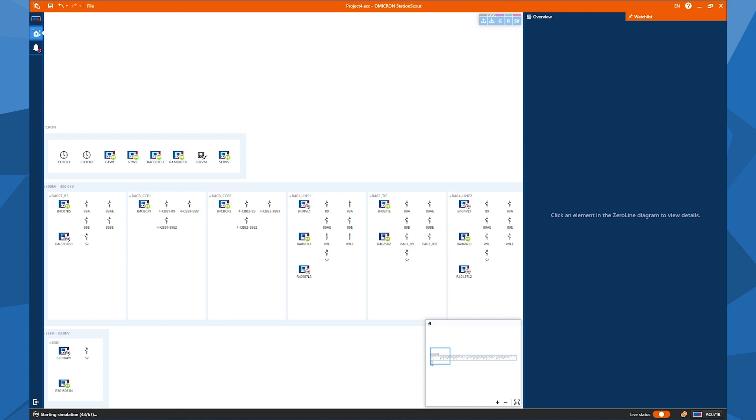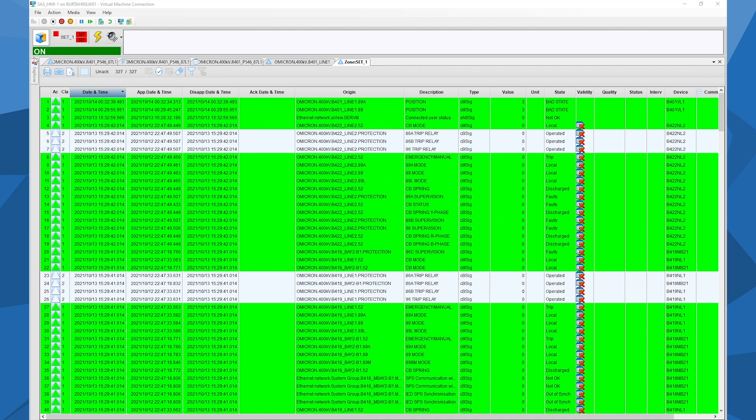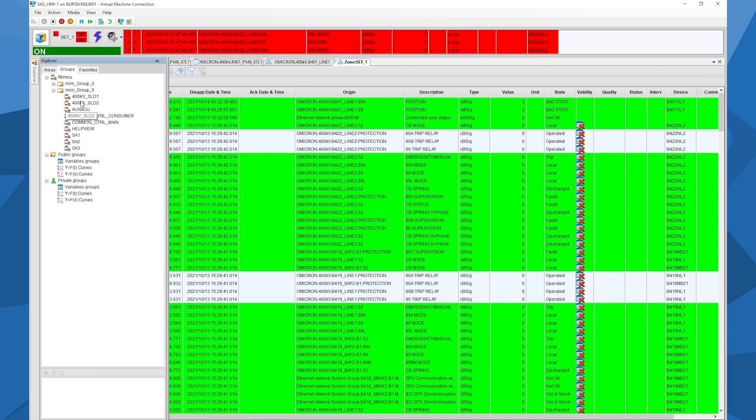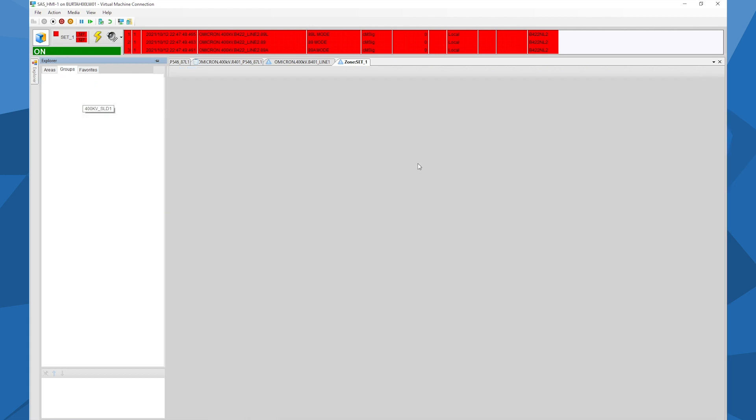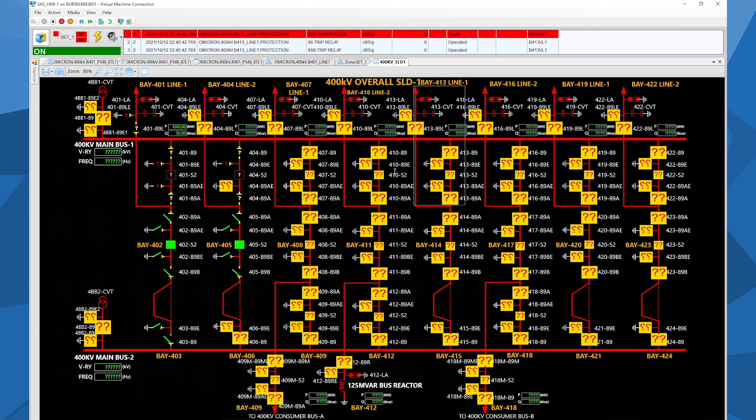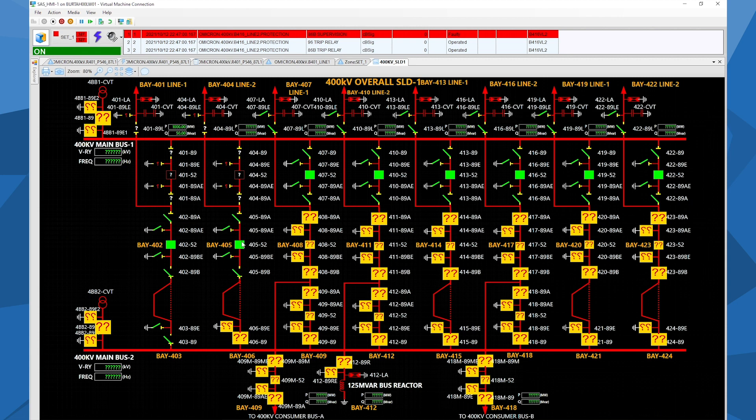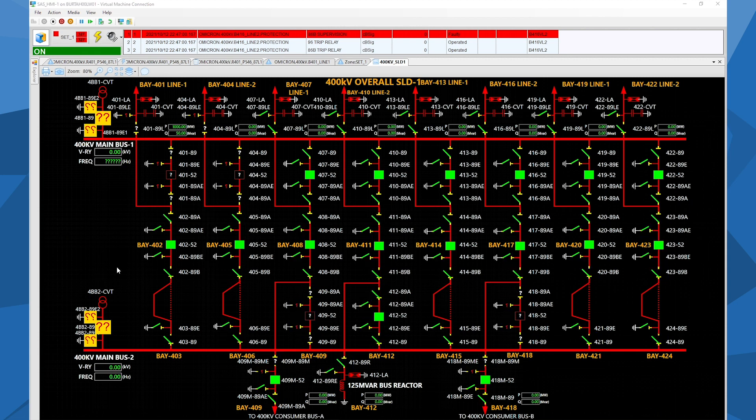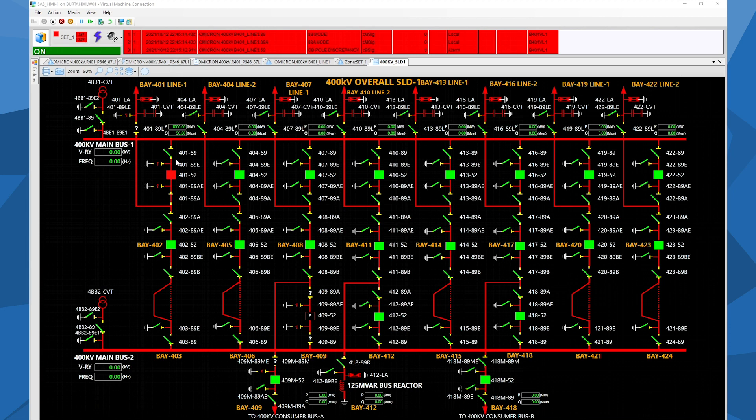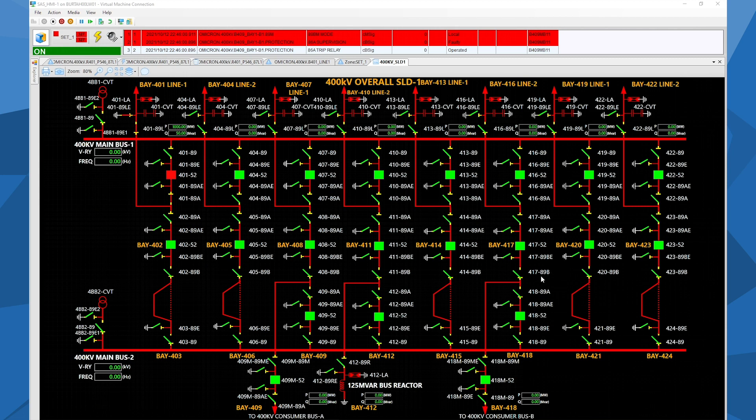Okay, so this shows us a hint that which IEDs we expect to see the positions and all the other signals which are communicating out to the SCADA. And when the HMI systems comes online, we can switch to the single line diagram, which is the general overview of the HMI that shows us all the bays and all the positions within the bays. So now you see that some of the bays have the valid positions taken from the Station Scout online, and some of the bays have not still appeared, and therefore you see them with the question marks, which means the invalid status of this bay and switch. So I think it's just one bay left. Yeah, that's also fine. So now you see all the switch positions are available here.